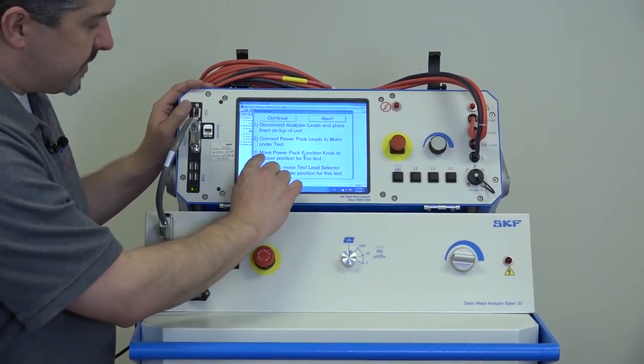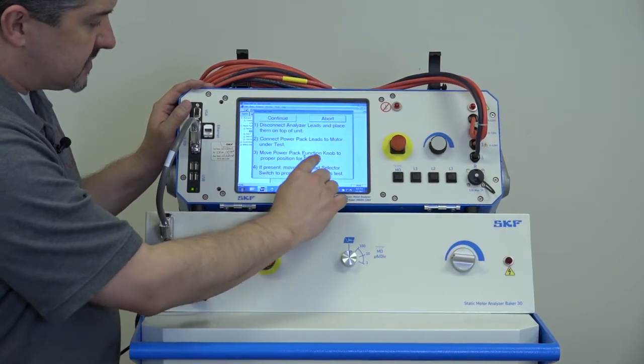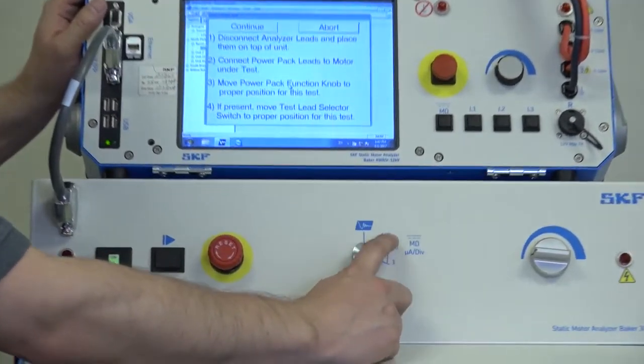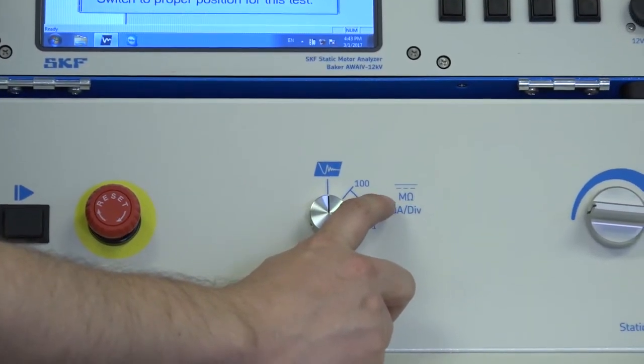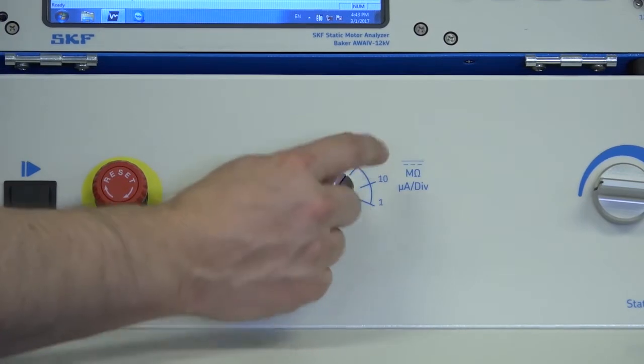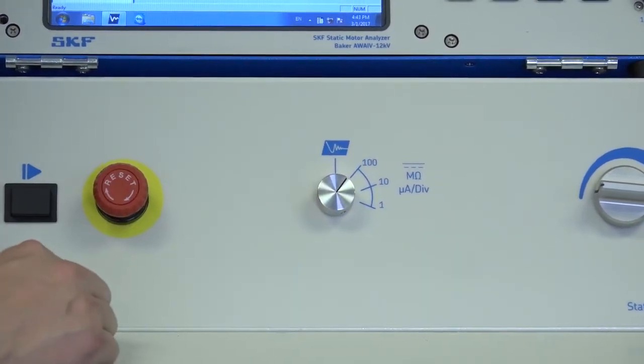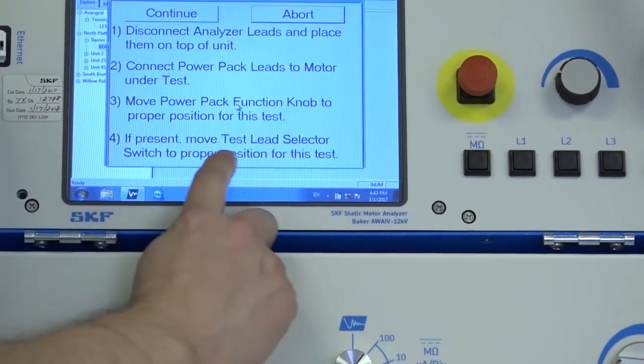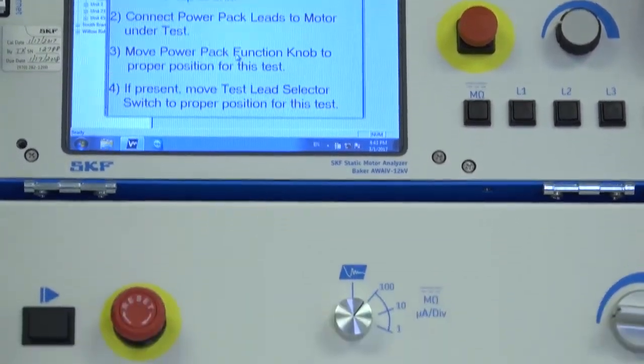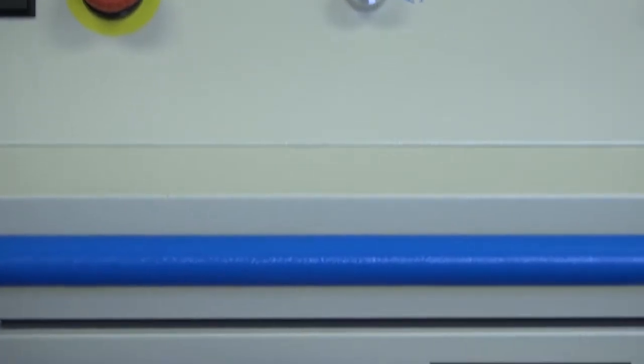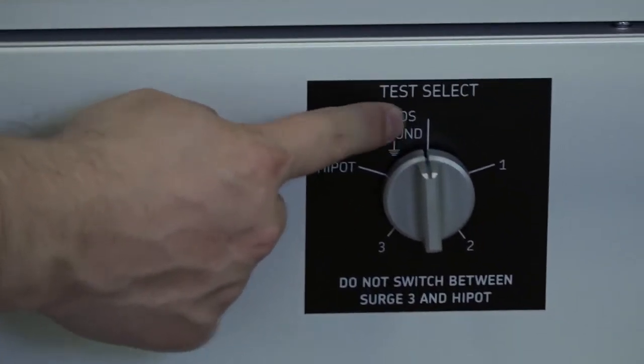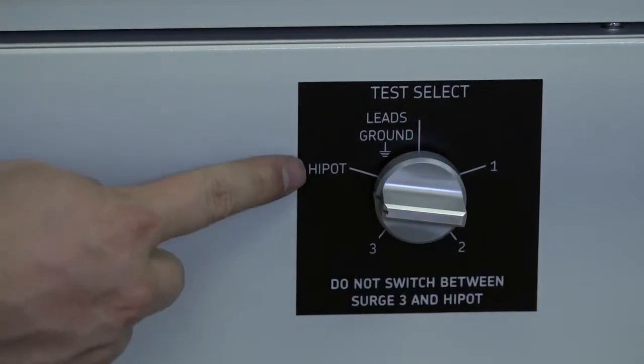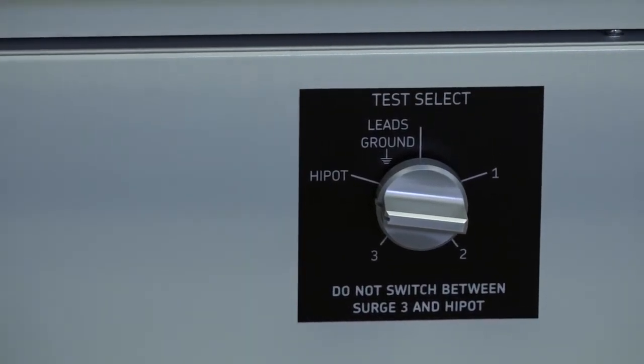Step three, move the PowerPak function knob to the proper position for this test. So since we're doing a high pot test, we have three positions for high pot: the 100 microamp setting per division, 10 and 1, and we always start on the highest, on the 100 microamp per division setting. Step four, if present, move the test lead selector switch to the proper position for this test. Down here, the lead selector switch, which should normally be placed in leads ground position, we'll turn that counterclockwise to the high pot position, and now we're ready to initiate the test.